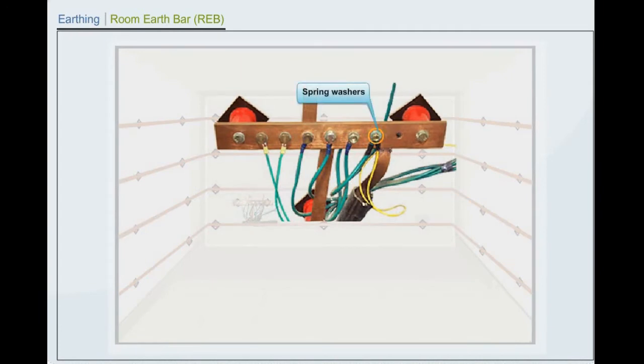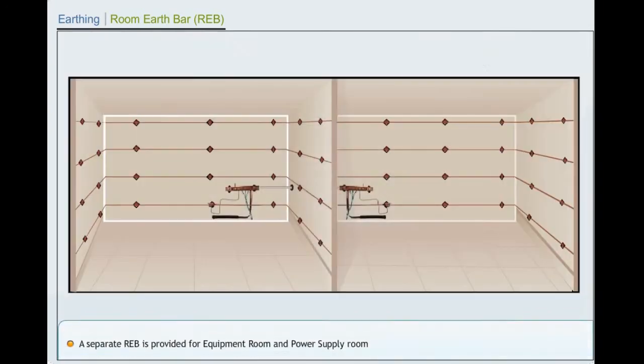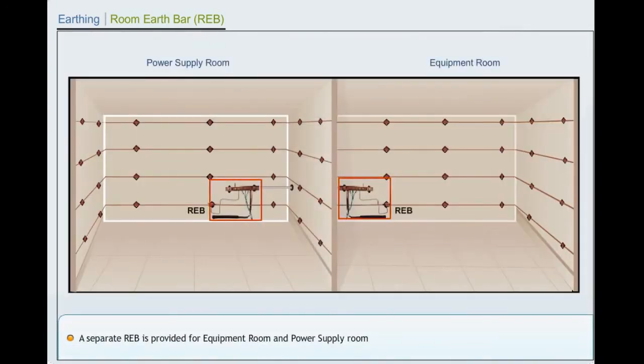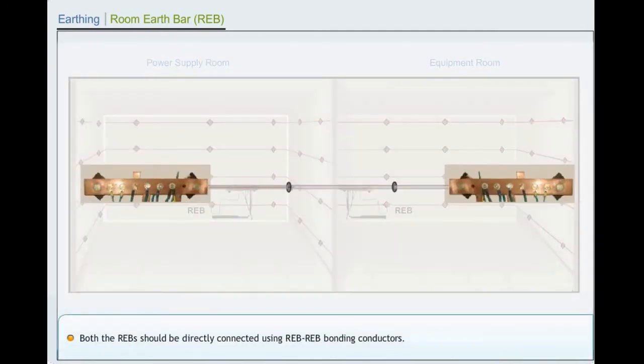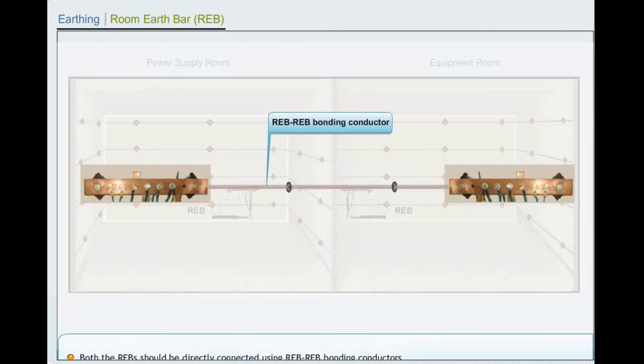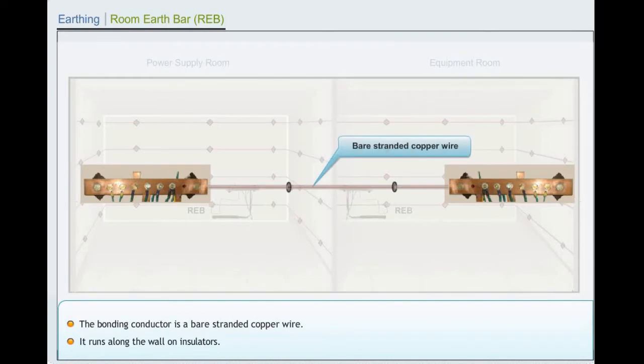However, the earth leads are bolted to the lugs. A separate room earth bar is provided for equipment room and power supply room. Both the REBs should be directly connected using room earth bar bonding conductors. The bonding conductor is a bare, stranded copper wire.